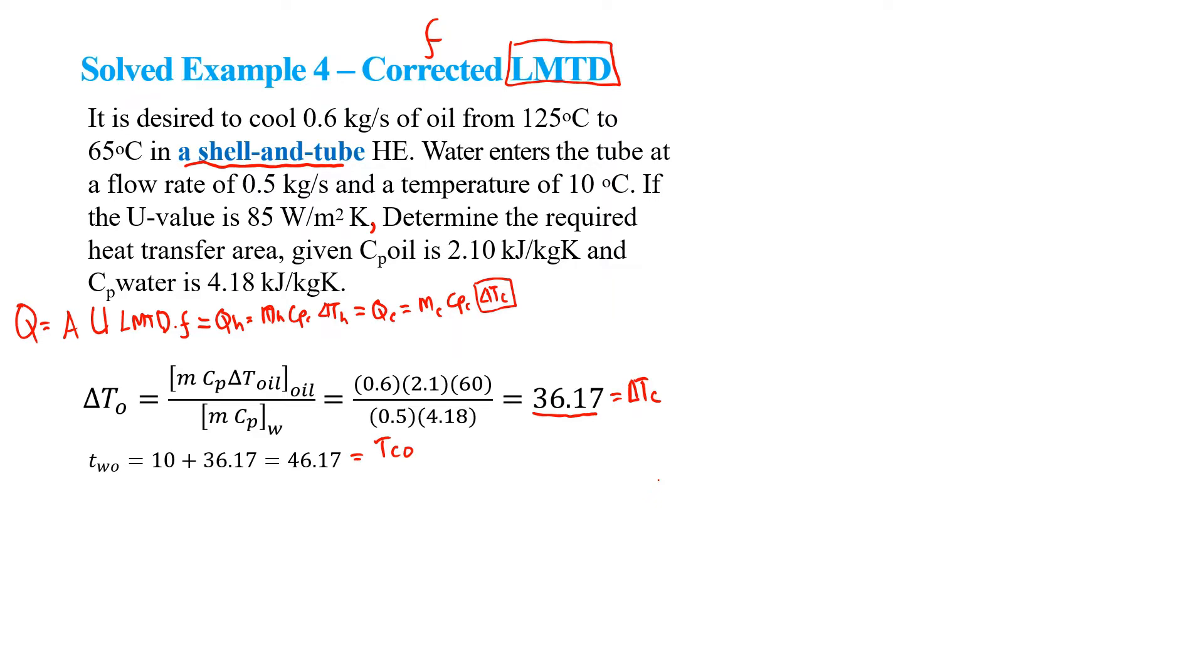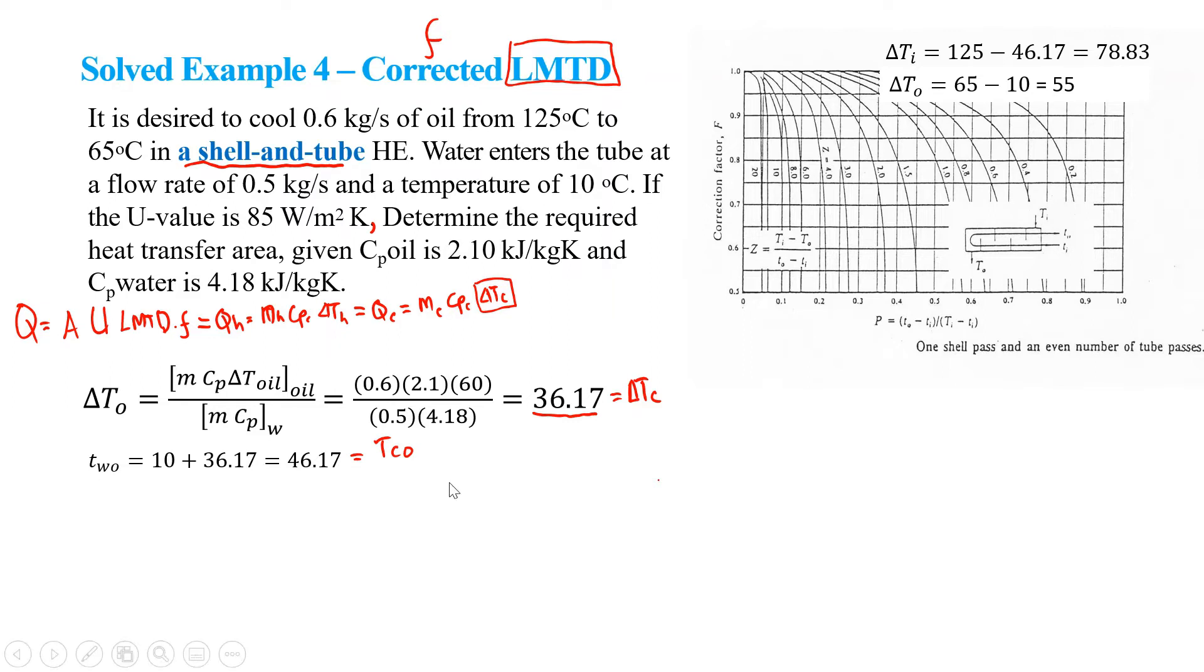What we do next is we need to find out the correction factor F, which can be obtained from the chart. This is the one for the shell-and-tube heat exchanger, specifically for one shell pass and even number of tube passes. You can have two passes of the tube, four, six, and so on. If not specified, you can choose either side, but in this example I will use the shell side as the oil for the hot fluid and the tube side is water.